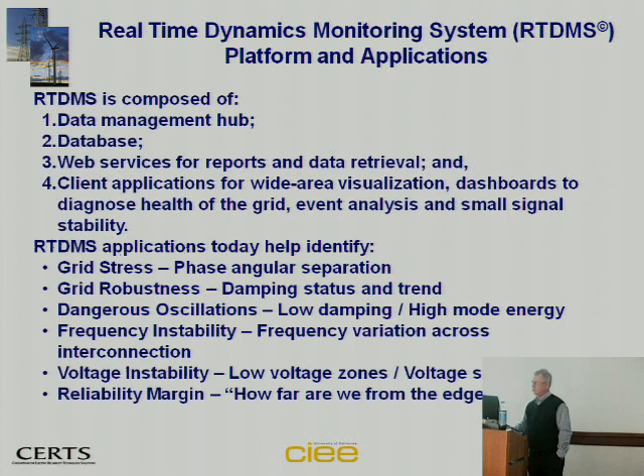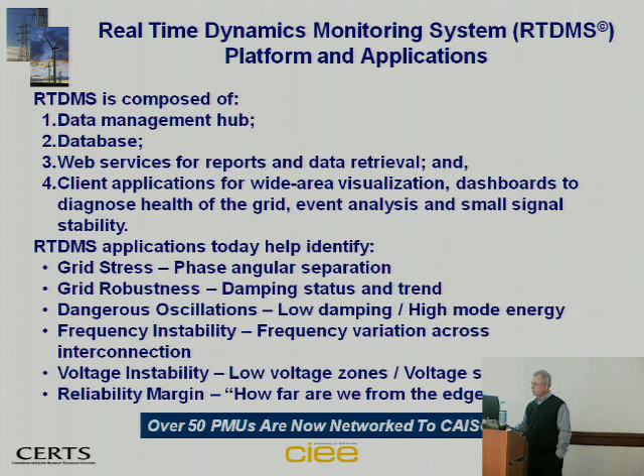RTDMS today can do grid stress indications through phasor angle separation — I'll show you an example — grid robustness through damping status and trend of low-frequency grid oscillations, and I'll show you one of those in a minute. It also handles dangerous oscillations, frequency instability, voltage instability, and reliability margins — in other words, how close we're operating to the reliability edge.